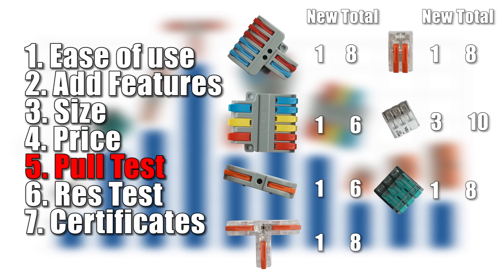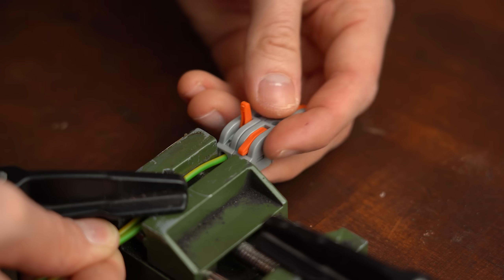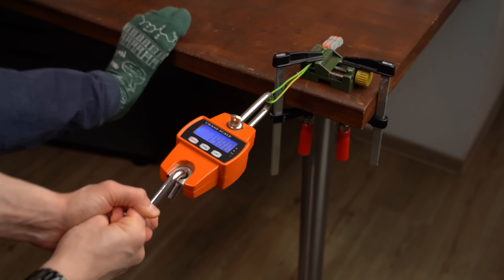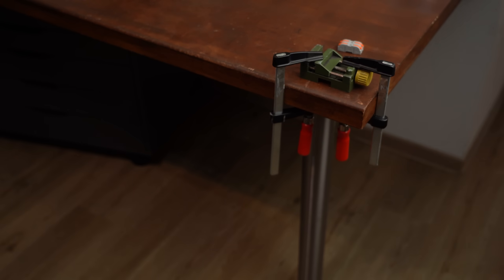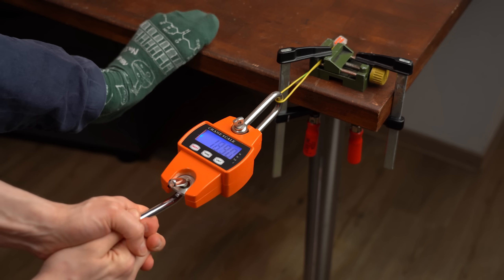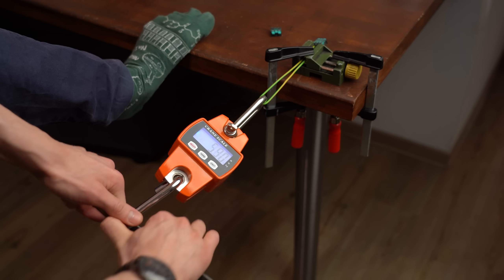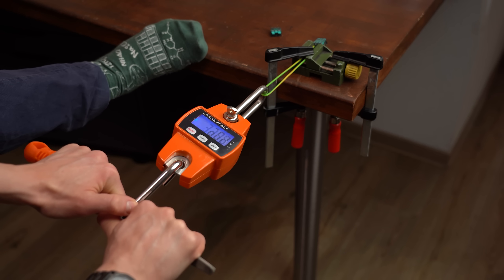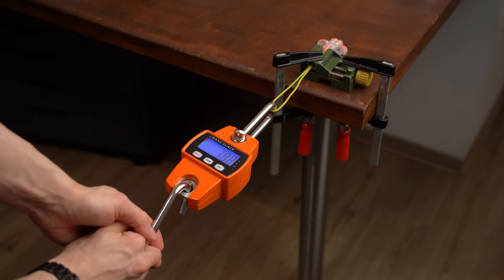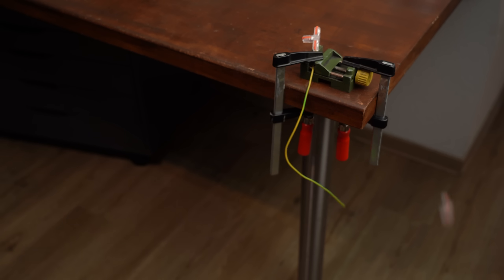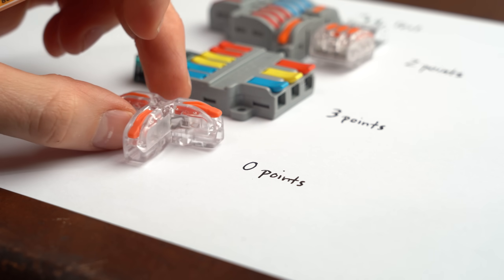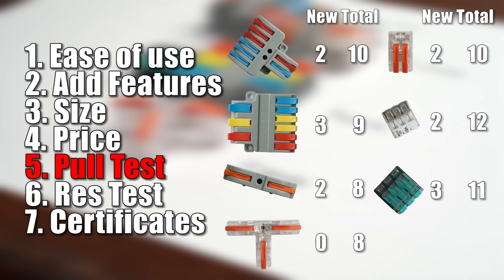So next we come to the pull test in which I simply placed a solid core conductor in the connectors which I then pulled out while measuring how much kg of force I needed to do that. For the most part, the results lay between 20-30kg, which I am only calling good here and not excellent because there were two connectors against whose gripping power I had no chance, therefore deserving 3 points. But on the other hand, there was also one connector that didn't really grab well and thus I could even remove wires with my bare hands, which I think is pretty bad.